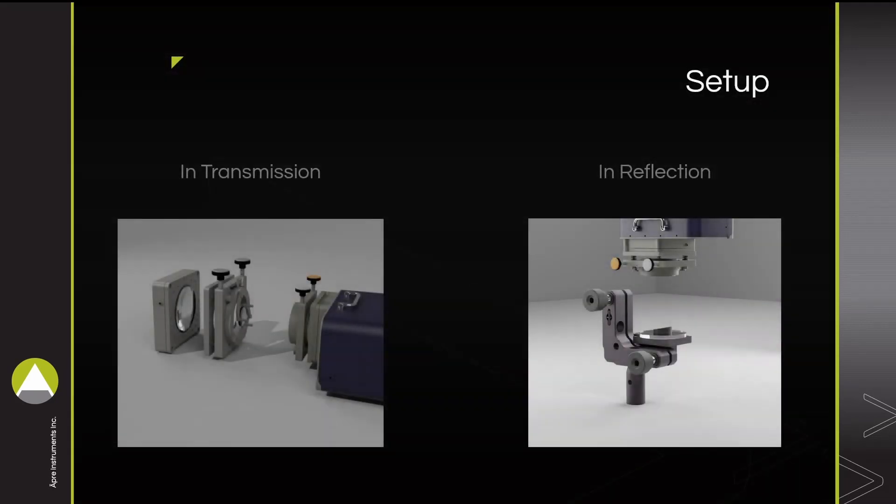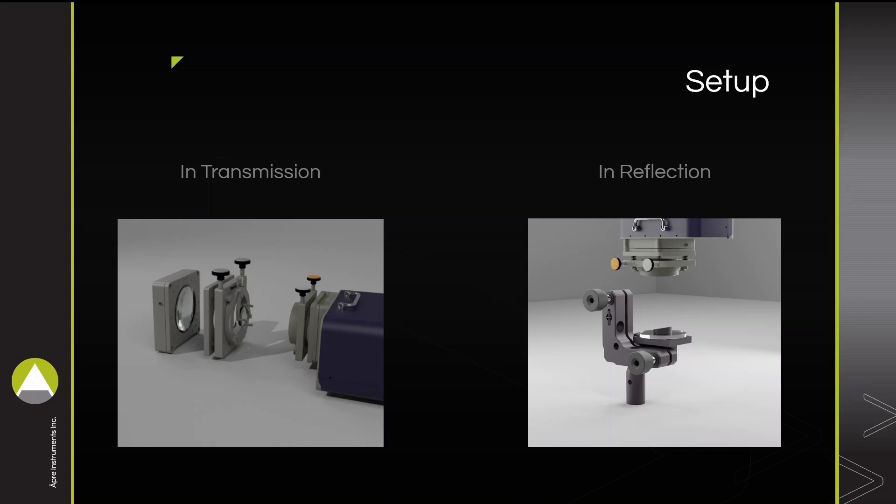Measurement setup is determined by wedge transparency. Transparent wedges are measured in transmission, where light passes through the part and reflects off the reference flat. If a wedge is reflective or opaque, it will be measured in reflection, where light is only reflected off the front surface of the part and does not pass through to reflect off the reference flat.